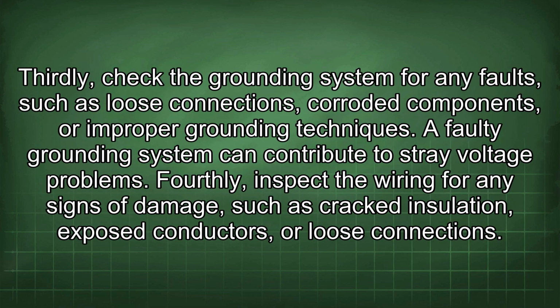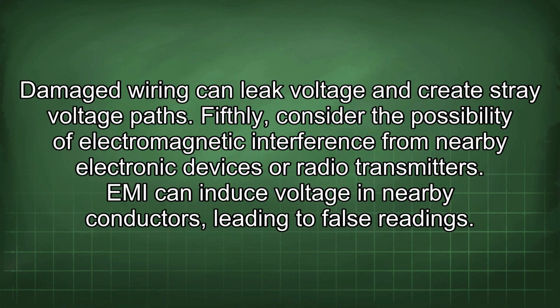Thirdly, check the grounding system for any faults, such as loose connections, corroded components, or improper grounding techniques. A faulty grounding system can contribute to stray voltage problems. Fourthly, inspect the wiring for any signs of damage, such as cracked insulation, exposed conductors, or loose connections. Damaged wiring can leak voltage and create stray voltage paths.